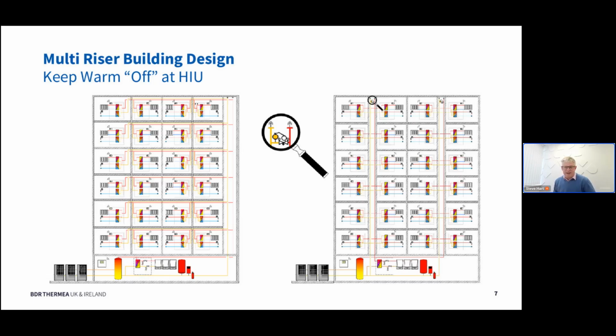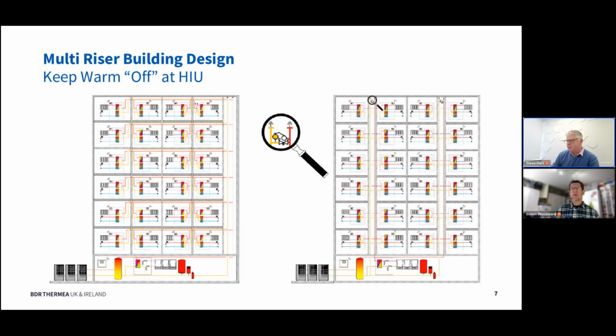The only thing you must then do is make certain that you install a thermostatic temperature control valve at the top of each riser, so you're maintaining heat in the riser, so when the HIU cools, it can go.